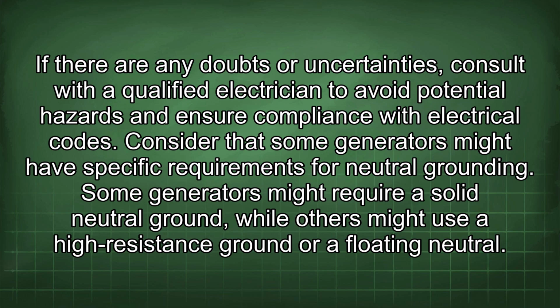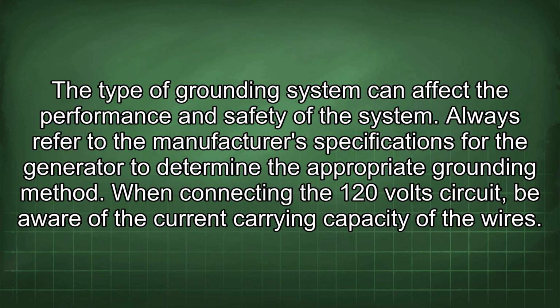Some generators might require a solid neutral ground, while others might use a high resistance ground or a floating neutral. The type of grounding system can affect the performance and safety of the system. Always refer to the manufacturer's specifications for the generator to determine the appropriate grounding method.